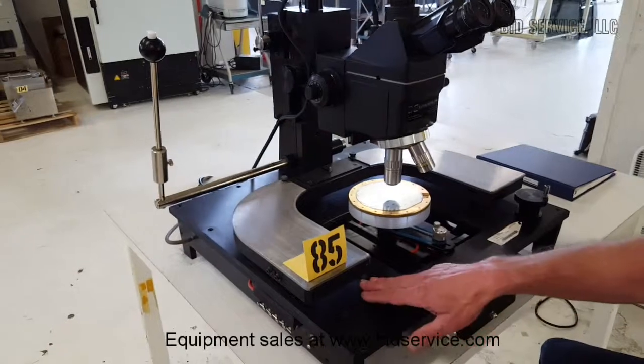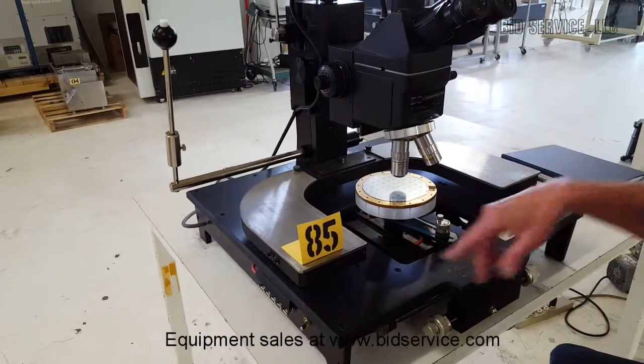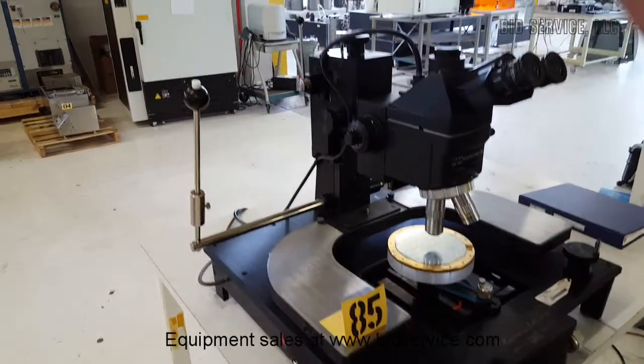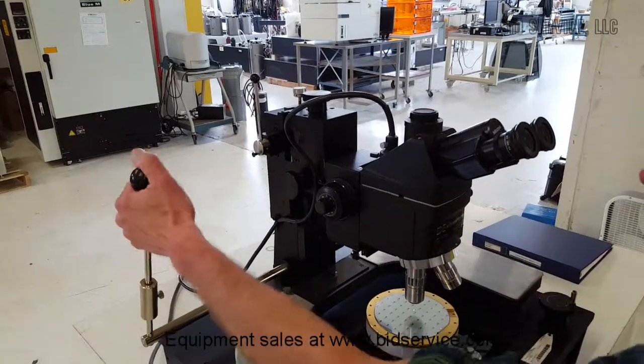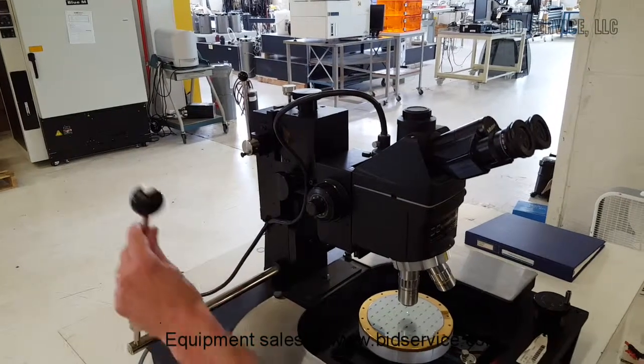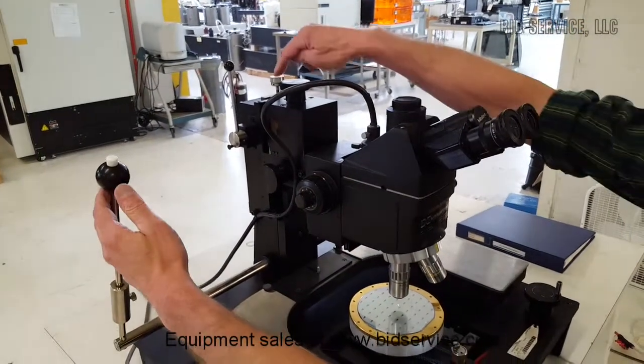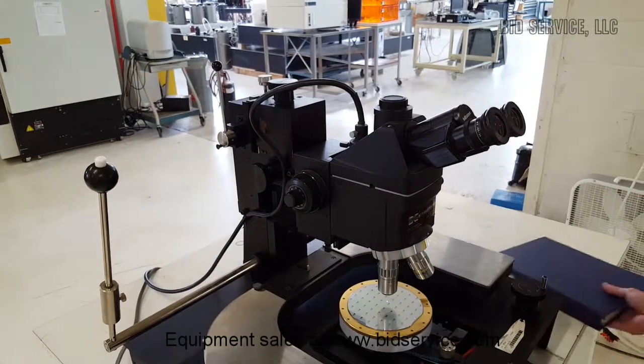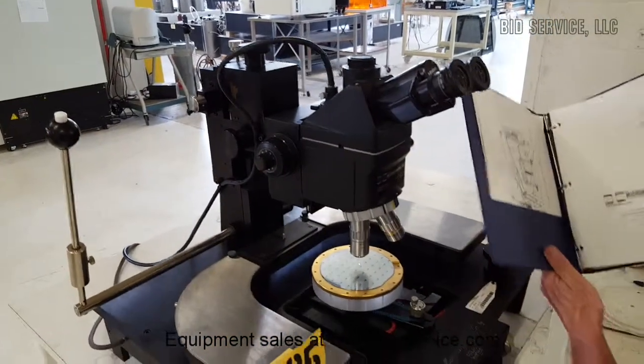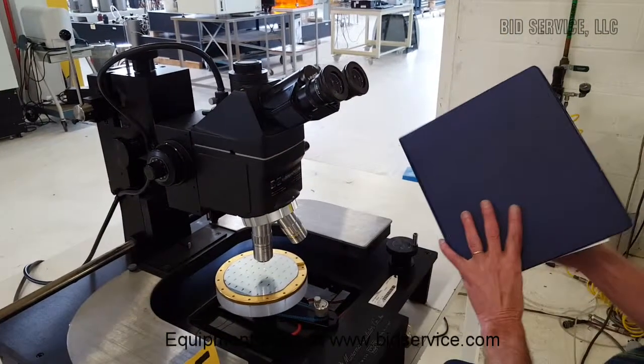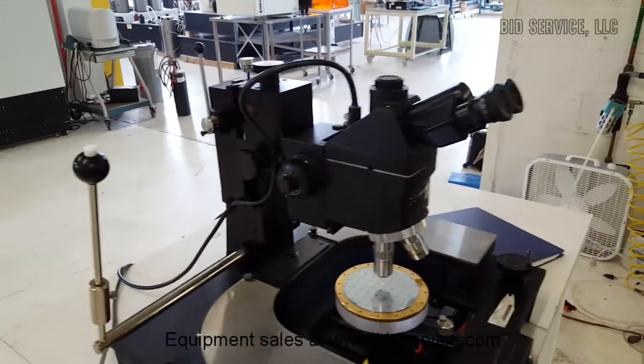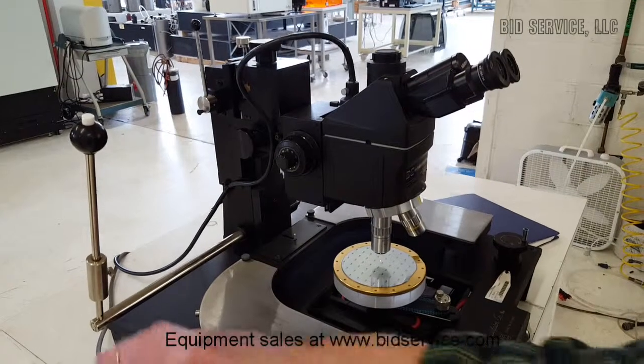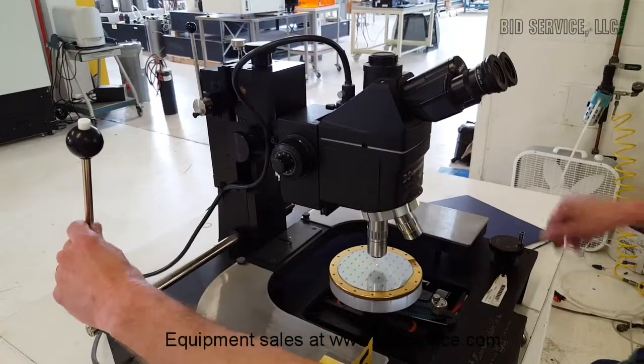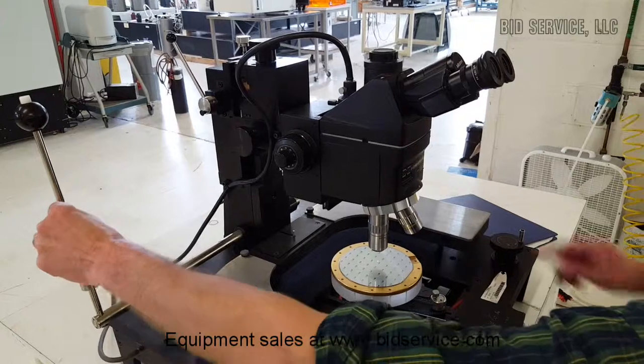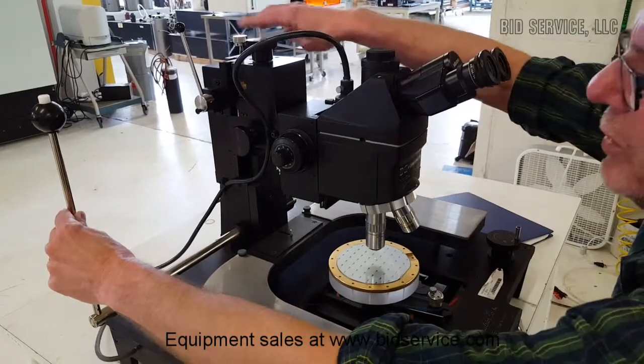As you can see, when I move the platen up one step, I set the lift delay for the microscope. As you can see, the microscope hadn't moved up on that as I moved up the platen. And it depends on where you set this knob back here. This will all be explained in the manual that you'll receive, explaining all the operations of the 6200. You'll receive a copy of that. But anyway, what I was trying to point out here is that I moved up one, the microscope didn't move. At this point you can see that the microscope is lifting up, and that's because I have a lift delay set here.